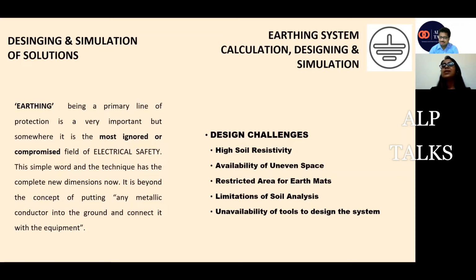The number of earthing pits depends upon the soil resistivity of that location, how much resistivity is there, and as per that we calculate the number of earthings, that in so and so number, say 10, of earthing pits we will be able to achieve less than 1 ohm, because earthing has a criterion that the resistance should be as low as possible. Every standard is saying that the resistance should be as low as possible. So keeping in mind the low figure, generally people design it for less than 1 ohm. It will be the lowest value. So for less than 1 ohm, the system will be designed.